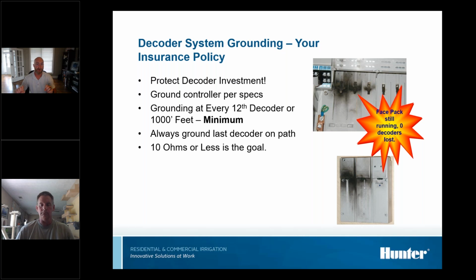Moving down the path, you always want to ground the last decoder on the path. What we're doing here with grounding is making the resistance on the 2-wire path 10 ohms or less. This can be tested with what we call a megger. Sometimes I've seen some of my irrigation consultant customers, if they specify a job, go out with a megger and test to make sure that the grounding line is ohming out at 10 ohms or less. So that's what we're trying to do.